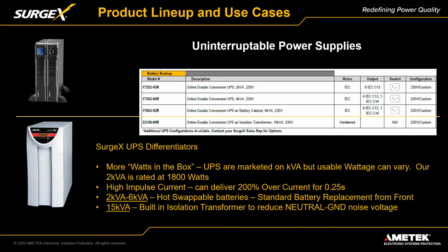The large format UPSs have built into them an isolation transformer, which is a very unique feature, allowing the system to have a new neutral to ground bond established. The neutral to ground noise in the electrical service is greatly reduced when you go through an isolation transformer. It also - though that last point's not important in your market - in the U.S. market, allows for simultaneous 120, 240 volt output, but you're 240 volt all the time, so that really doesn't matter to you guys.